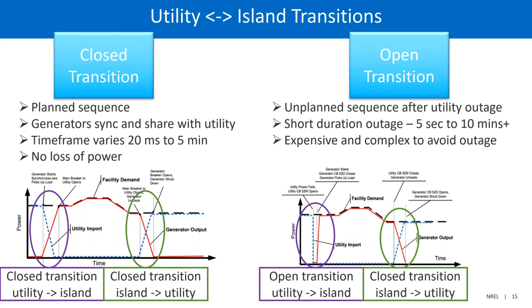There are ways to avoid that short outage, but typically they're expensive and complex to implement and not typically done. So typically, the open transition is what happens when the utility goes out, and then all other transitions are closed. So usually the only time you have a loss of power is when the utility goes down. All right, next slide.